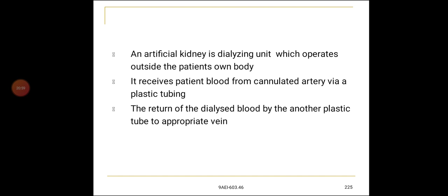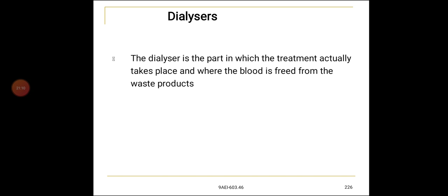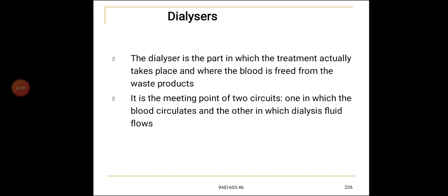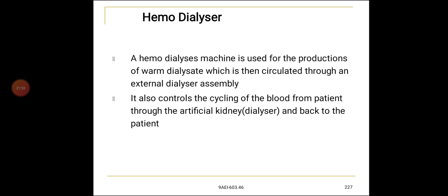Dialyzer. The dialyzer is the part in which the treatment actually takes place and where the blood is freed from the waste products. It is the meeting point of two circuits, one in which the blood circulates and the other in which dialysis fluid flows. Hemodialyzer. The hemodialyzer machine is used for the production of warm dialysate, which is then circulated through an external dialyzer assembly. It also controls the cycling of blood from the patient through the artificial kidney, that is the dialyzer, and back to the patient.